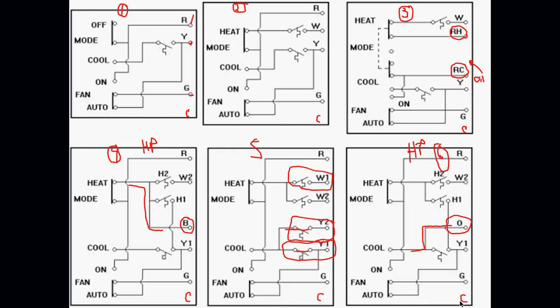Okay, so if a homeowner has one of these old thermostats, let's say they have number 2 mounted on their wall, okay, and it's a little round thermostat, has mercury in it, and it's an older style thermostat, and they want to install a programmable thermostat without batteries, okay? You might not be able to do it if you don't have a spare thermostat wire. So when you're running new thermostat wire, you always want to go one conductor higher than you need. So there's a spare wire there in case anybody ever needs to change anything in the future. It's always nice to have a spare wire. You can always pull new thermostat wire, but sometimes that's very, very difficult to do.